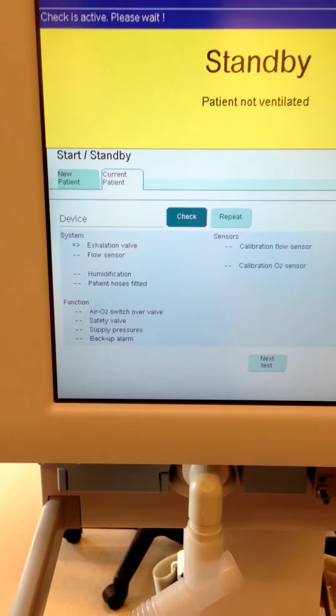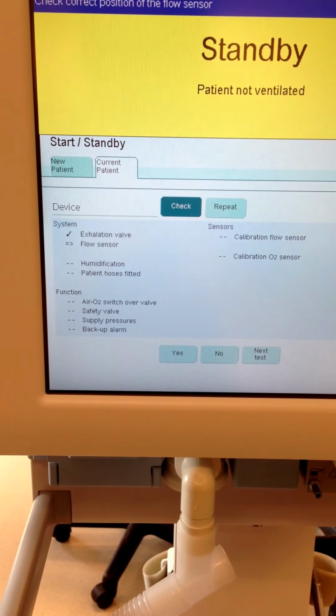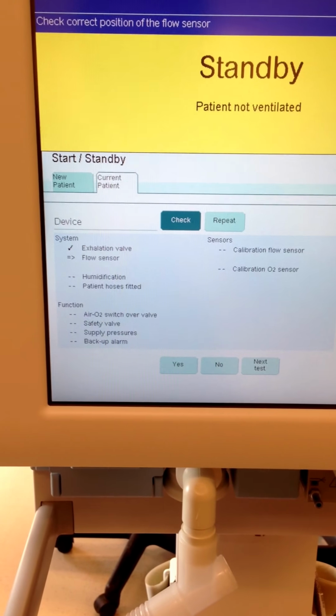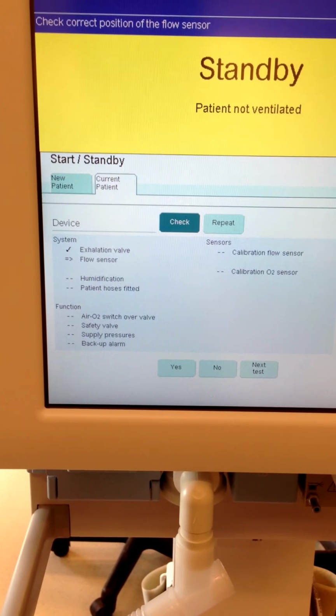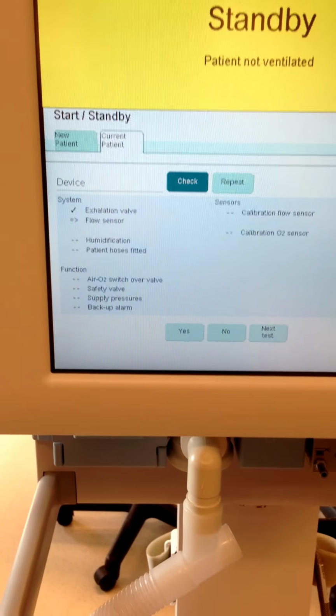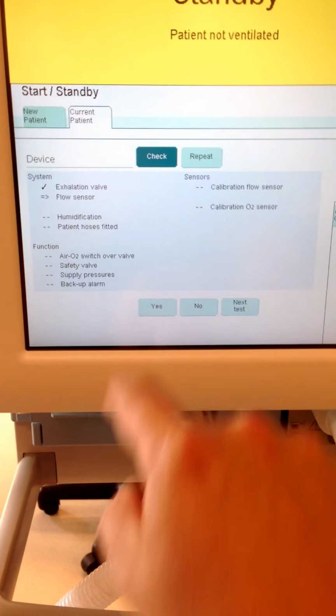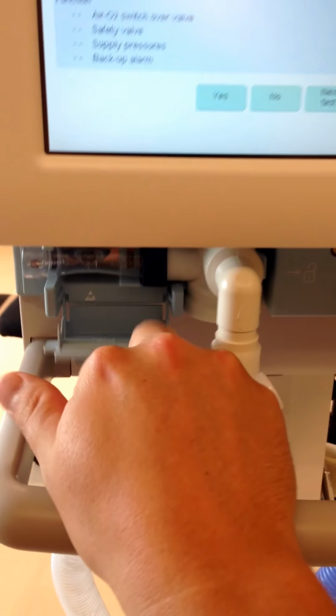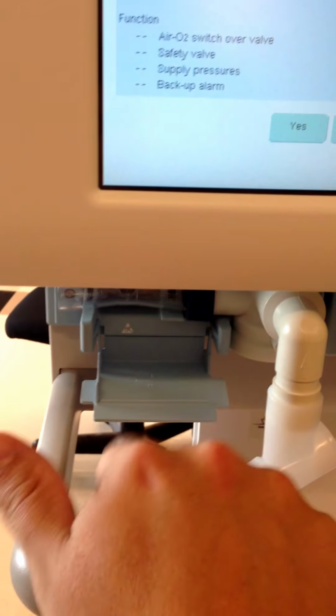Okay, so now we're going to be doing the exhalation valve and the flow sensor. It's asking me to check the correct position of the flow sensor. I know that's correct because we just installed it with the assembly, so I'm going to go ahead and say yes.